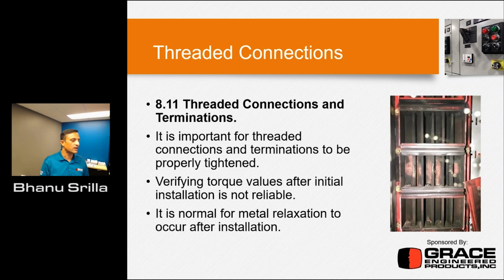So verifying the torque values of initial installation is not reliable. Some people say that, hey, I'm just bringing in the equipment from the manufacturer side who shipped it to me. Do I need to retorque this? Yes, absolutely yes, because there's a high possibility, because of the storage requirements or because of the transit requirements or the shipping, these contacts would have gotten loosened, right? You need to make sure that you go and recheck the torque values. It is normal for the metal relaxation also to occur after installation time.